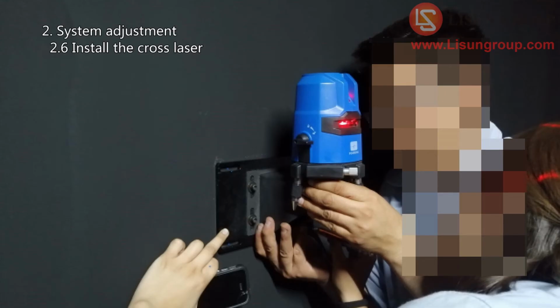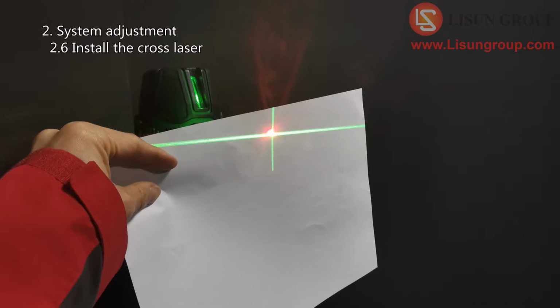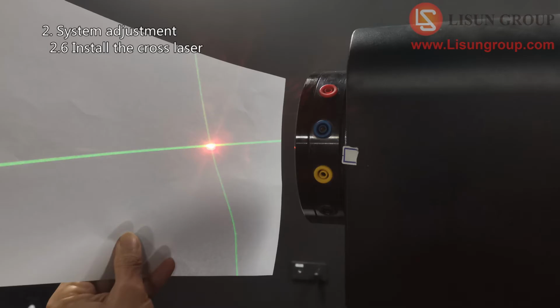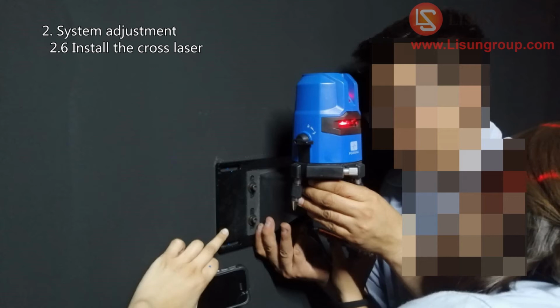Turn on the cross laser. Put the triangular metal support on the wall. Adjust the position of the support, the direction of the cross laser. Make sure that the center of the cross laser is completely coincident with the laser from the main arm of the goniophotometer. It should also be noted that the support of the cross laser is in a horizontal state. If not, the device will sound an alarm.